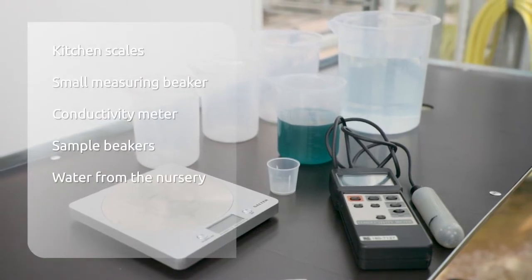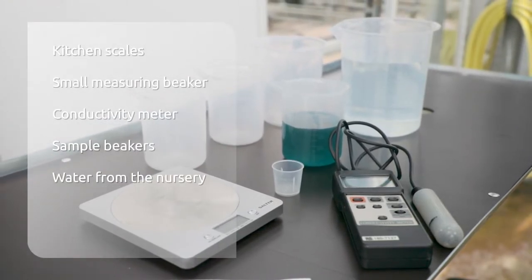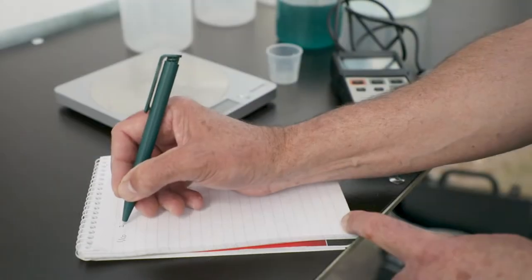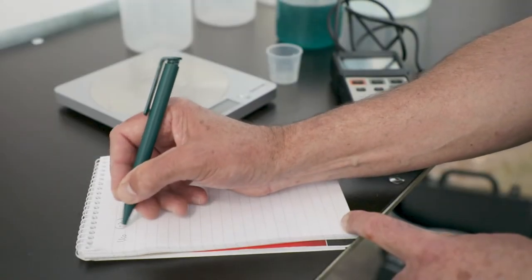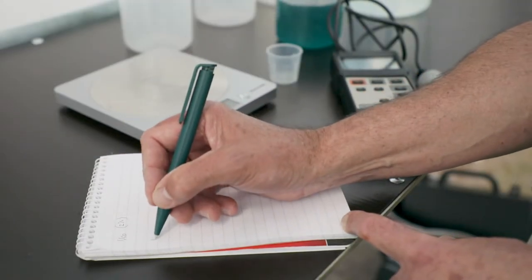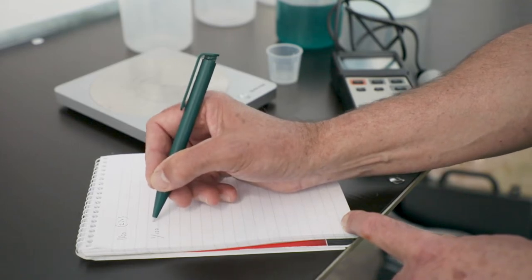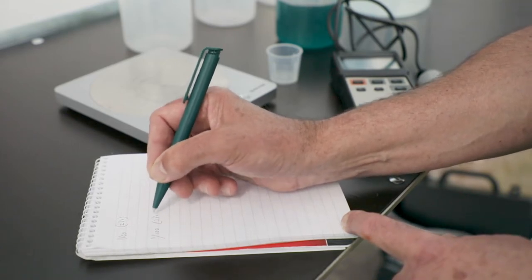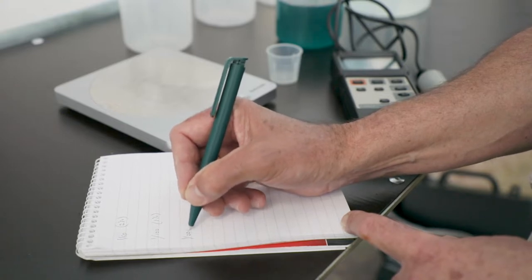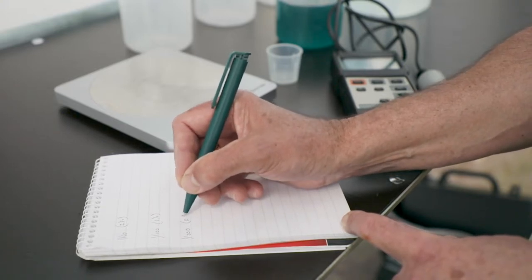We're going to check how effective the proportional diluter is to make sure it's giving the correct output conductivity. So we're going to start with a one in fifty dilution which is two percent, one in one hundred dilution one percent and one in two hundred dilution point five percent.